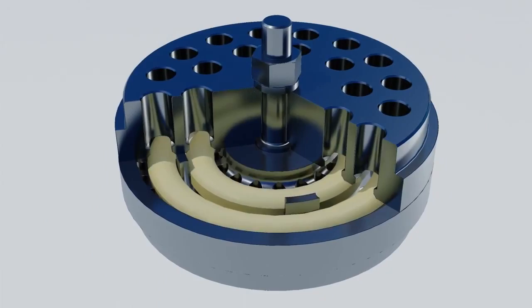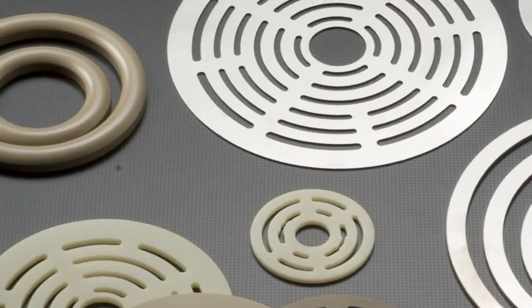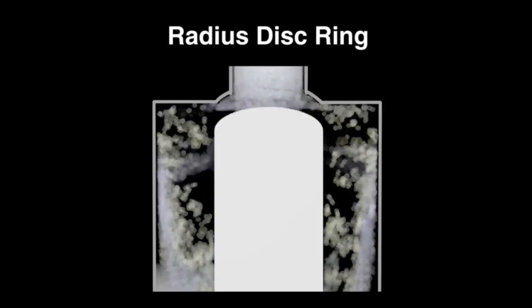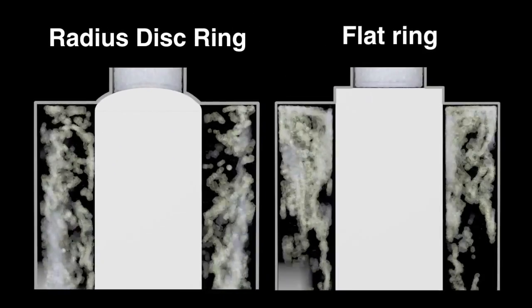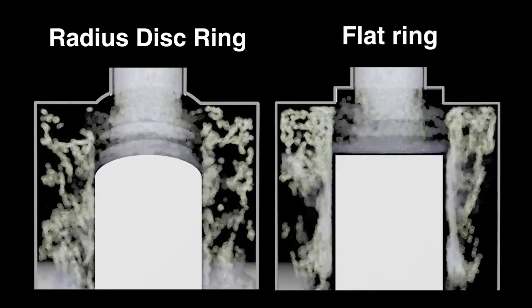The ring material is produced from a wide range of advanced thermoplastics chosen to specifically match your operating conditions. Thermoplastics are extremely resistant to the adherence of small particles, sand or salt, unlike their metal ring counterparts which will nick, wear, warp or crack under similar conditions.